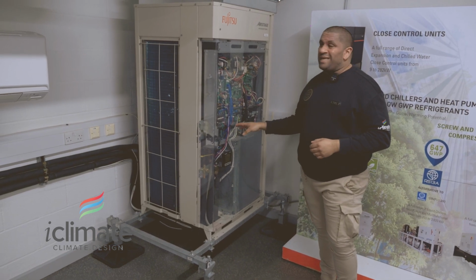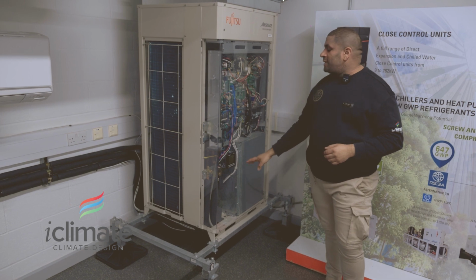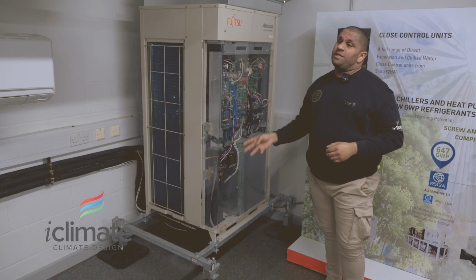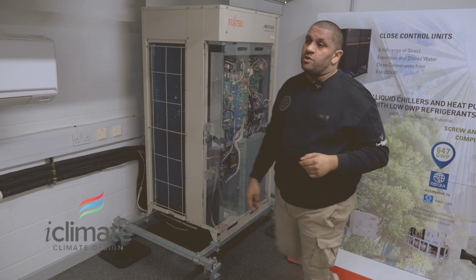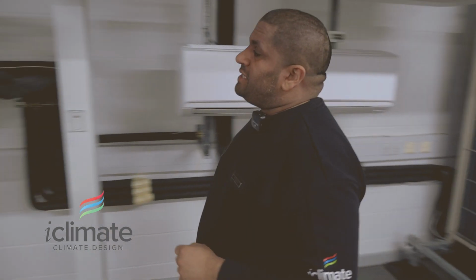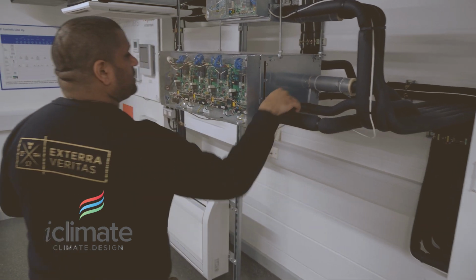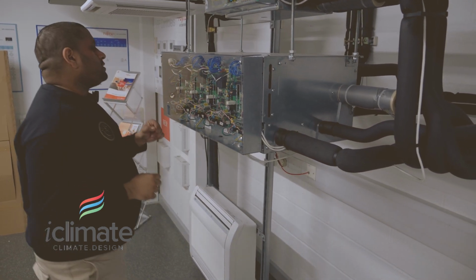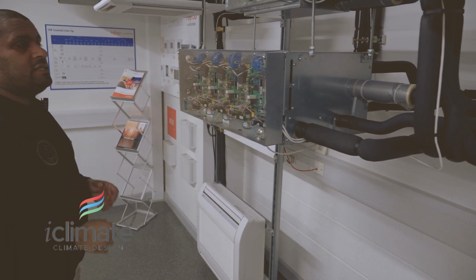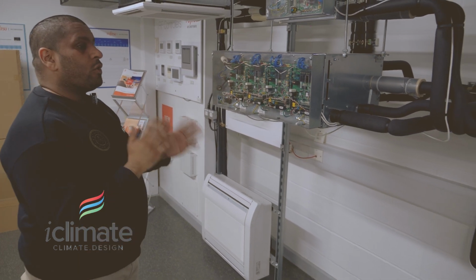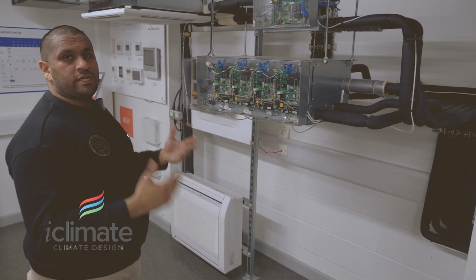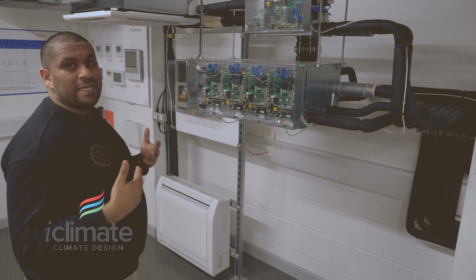So what's next to me here is a Fujitsu AirStage inverter. This feeds three pipes from the condenser. These three pipes run into a central distribution box, which is over here. This central distribution box, as you can see, has the three inlets here, and it then has multiple port outlets where it can feed the associated fan coil units and send the required state of refrigerant to the correct fan coil unit, whether it needs cooling or heating.